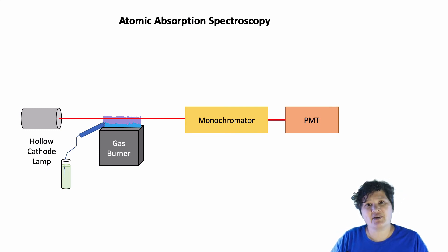Now, one way in which the setup differs from the UV-vis spectrometer that we're looking at in class, is that here the monochromator is after the sample, but before the detector, whereas in the UV-vis, it was before the sample. So, I want you to spend a little bit of time thinking about why there are these two different setups, and then we're going to talk about it in class.